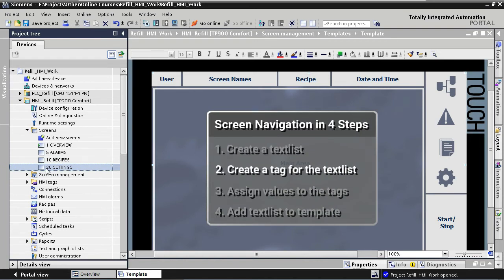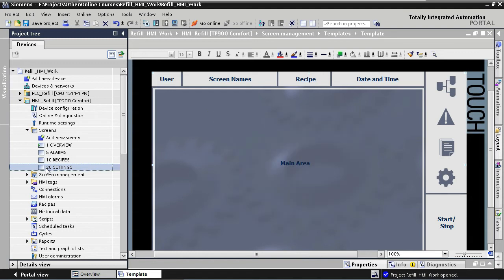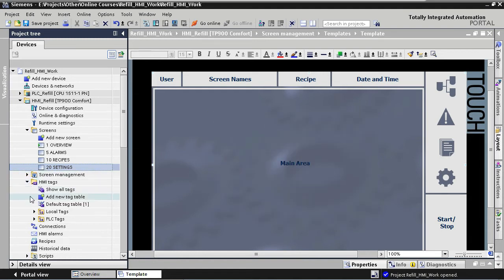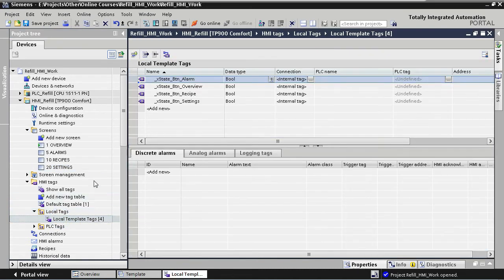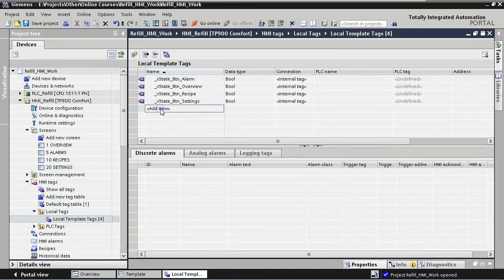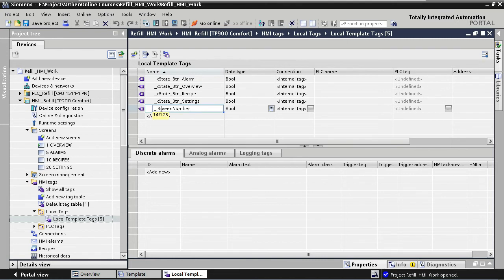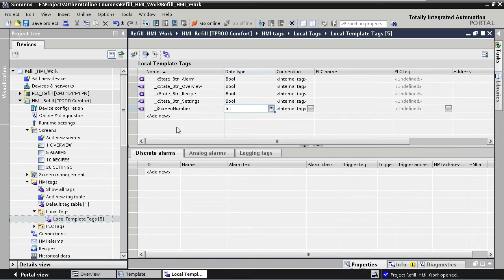In step 2, we're going to create the tag that we'll use together with the text list. This tag will be a local tag, and it will be part of the template tags. So we open the local template tags table. We are going to name our new tag screen number. The data type is integer. And for local tags, the connection is set to internal tag.